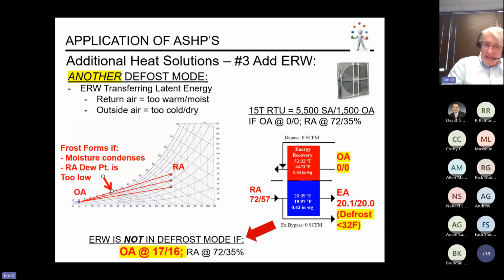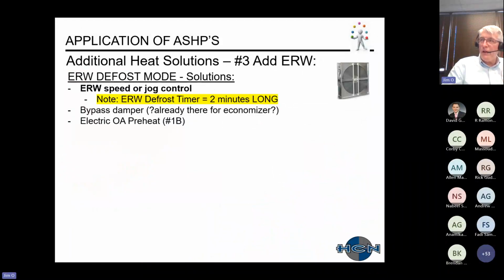Just playing devil's advocate, once again, just looking at different applications. If I raise my outside air temperature to those conditions, then my exhaust air temperature is going to be above 32 and not have defrost. Just realize when your unit's energy recovery wheel goes to defrost, the timer is much longer in duration. There are different types where they can jog. Jog's a nice name for on-off control.